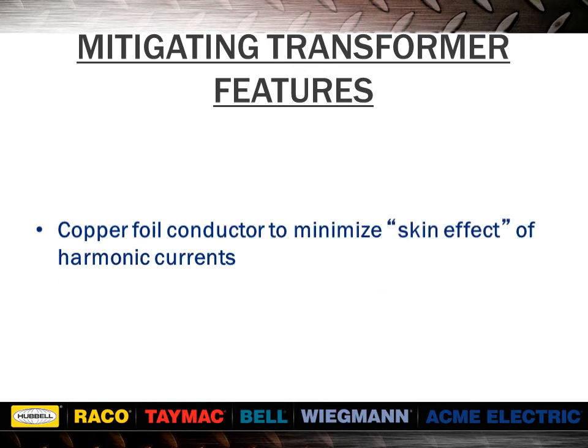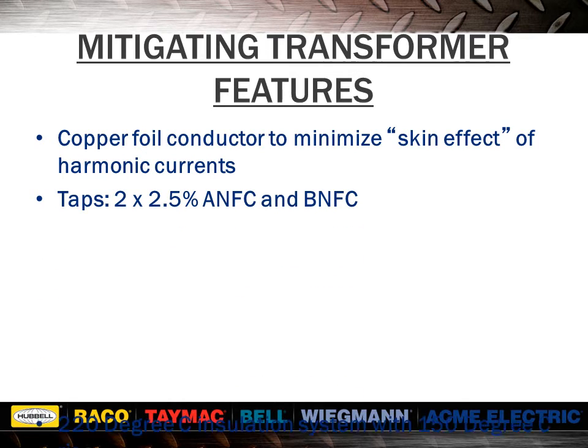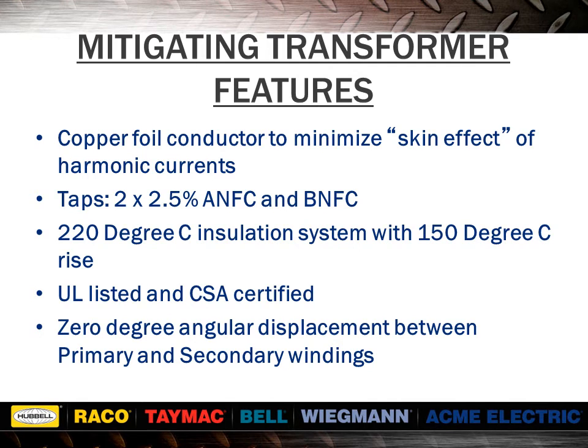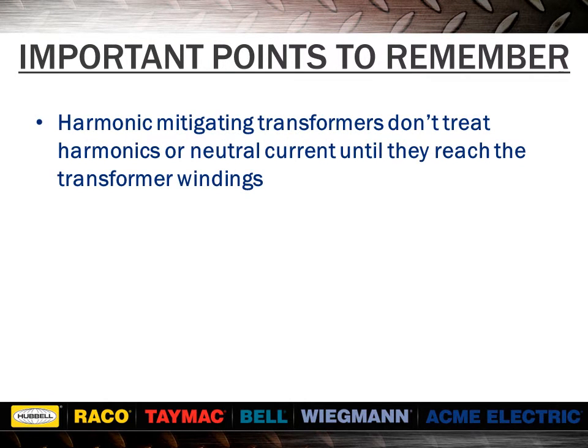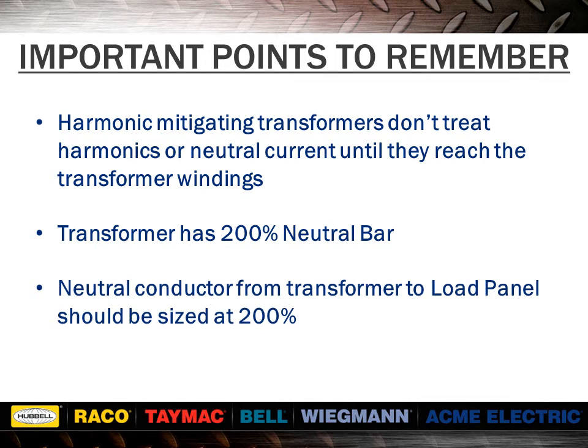Mitigating transformer features include copper foil conductor to minimize skin effect of harmonic currents, two taps at 2.5% above and below nominal, 220 degrees Celsius insulation system with 150 degrees Celsius rise, UL listed and CSA certified, and 0-degree angular displacement between primary and secondary windings. Harmonic mitigating transformers don't treat harmonics or neutral current until they reach the transformer windings, and they include a 200% neutral bar. The neutral conductor from the transformer to the load panel should be sized at 200%.